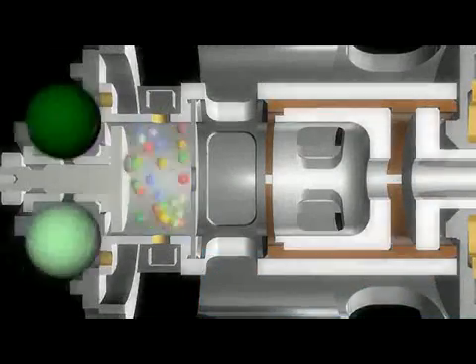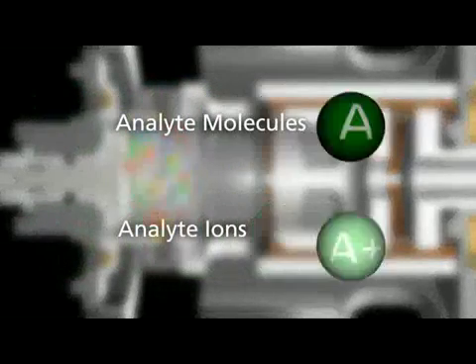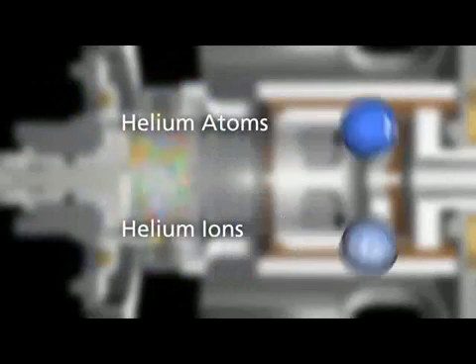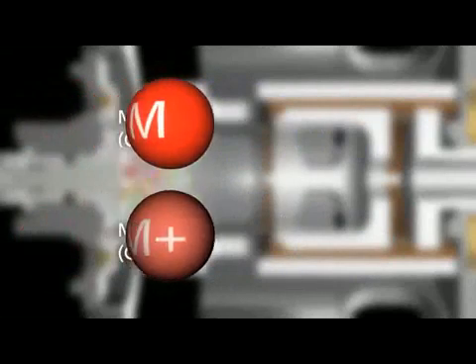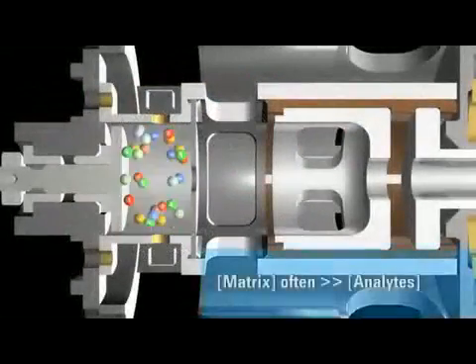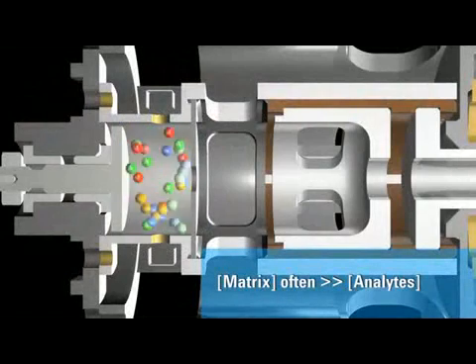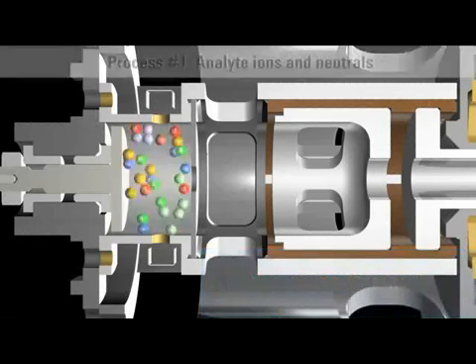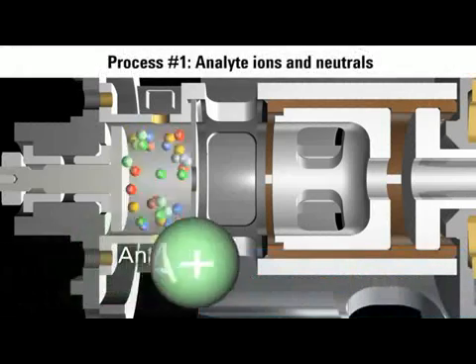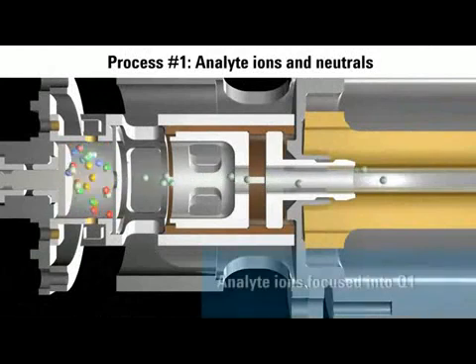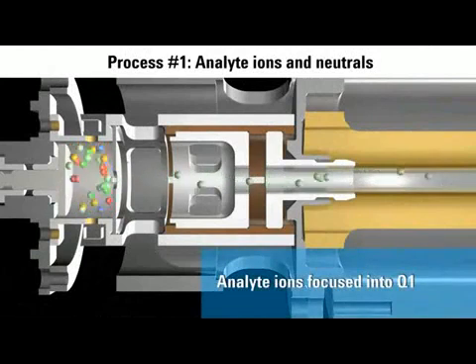So a thorough description must include analyte neutrals and ions, helium neutrals and ions, column bleed neutrals and ions, and many more neutrals and ions from the matrix at concentrations typically higher than the analyte. To simplify the description, let's start with the analyte molecules and ions. Analyte molecules enter the vacuum source from the GC capillary column and begin bouncing off the hot surfaces of the source.